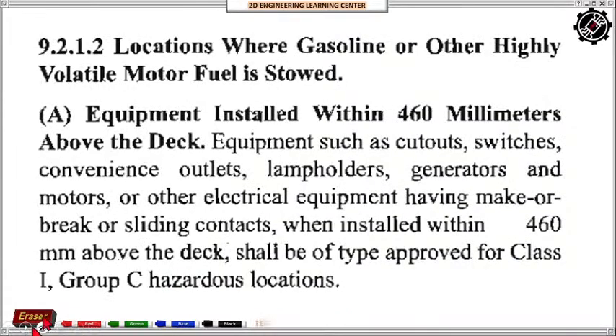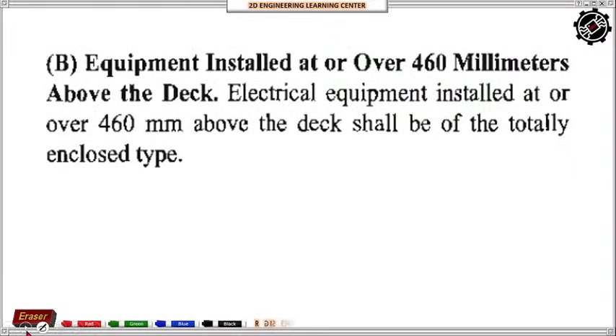Yeah. Tapos, locations where gasoline or other highly volatile motor fuel is stored. So, the equipment installed within 460 mm above the deck shall be approved for Class 1 Group C hazardous application pa rin. Kung lahat ng mga equipment doon, including the outlets, lamp holders, generators, and motors. Equipment installed at or over 460 millimeters above the deck shall be of totally enclosed type. So parang yung kanina lang din.